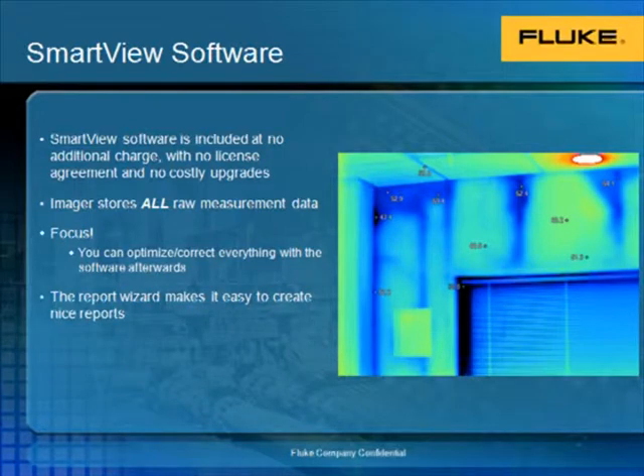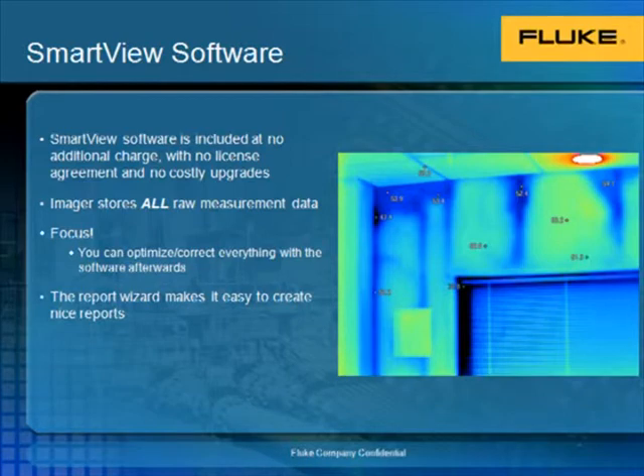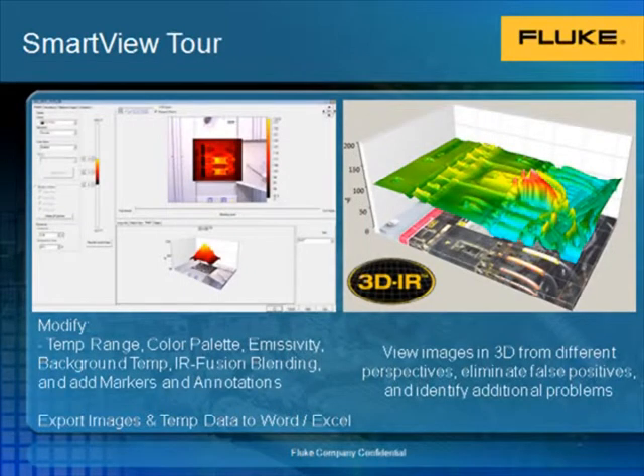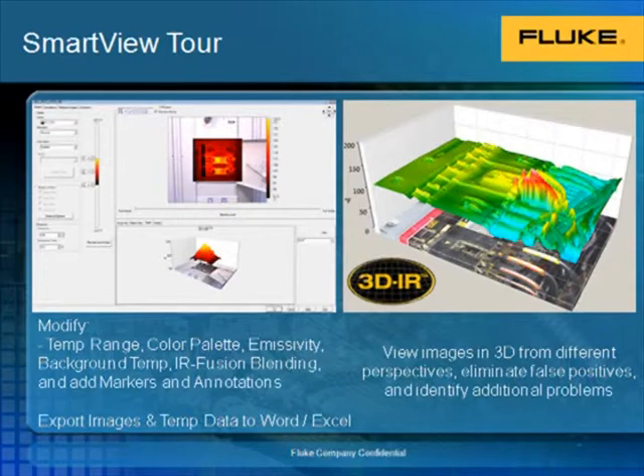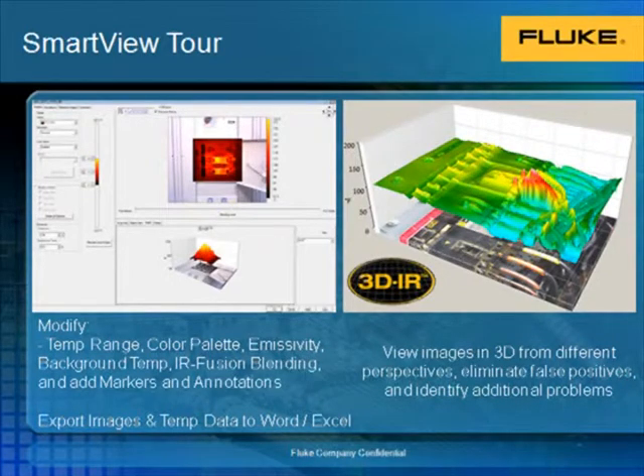I'd also like to stress the importance of focus. As long as you have the focus correct when you capture the image, all kinds of corrections can be made after the fact in the software. SmartView also has a report wizard that makes it very easy to create professional-looking reports. On the left we see the image edit function within the software. This allows you to modify the temperature range, color palette, emissivity, background temperature, the IR Fusion blending level, as well as add markers and text annotations. This also allows you to export images and temperature data to either Word or Excel.